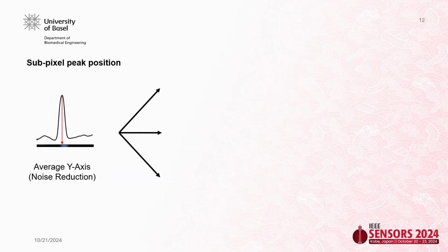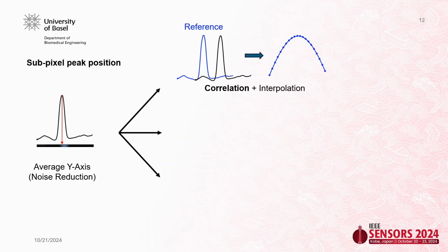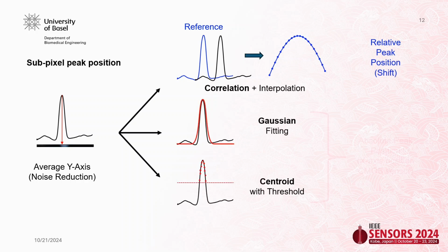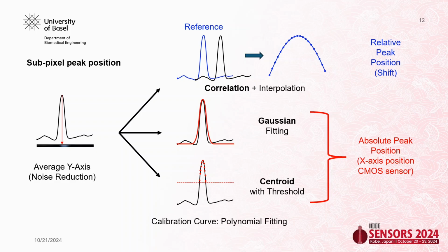And then we tested three different algorithms to find the peak position with sub-pixel accuracy. We first used correlation, and then we interpolated the correlation curve. We also used Gaussian fitting and the centroid algorithm. The first one gives us the relative position between the reference image and the one that we have, while the other two give us the absolute peak position along the x-axis of the CMOS sensor. And now with this information and the corresponding angle for every peak position, we could generate our calibration curve using a polynomial fitting.